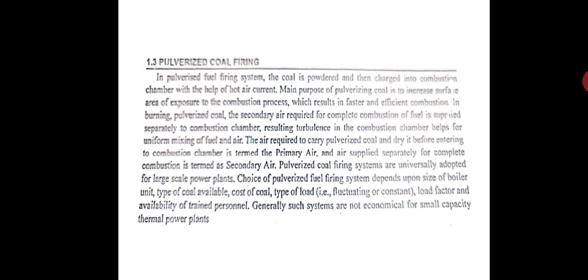So what are the advantages of using pulverized coal? First, a wide variety of low grade fuels can be used, like low grade coal which contains a lot of ash, and it can be burnt easily. Greater surface area is exposed to combustion, hence combustion is faster and efficient. The system is free from clinker and slagging problems. Combustion control is easy because it is in powder form. You can control the flow easily, and hence the system gives fast response to load changes. In case of high or low power requirement, you can change the flow rate easily. Then preheated secondary air can be used.